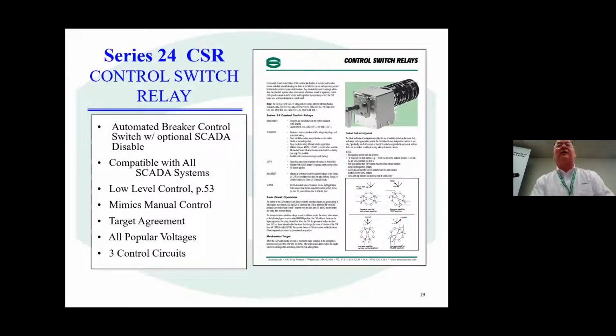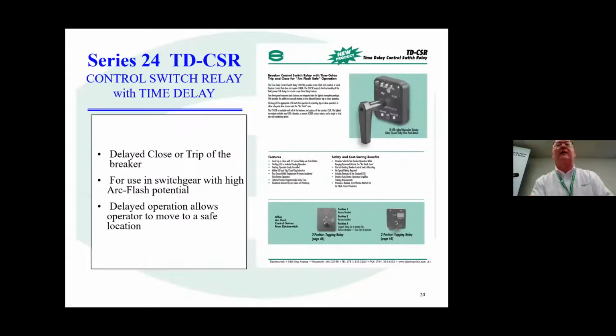So now we're going to talk a little bit about a special control switch. This is essentially taking a manual switch and putting a solenoid on it to electrically operate it, and then to provide SCADA outputs, as well as allowing it to be manually operated or SCADA operated, and then looking at the different types of configurations you'd want to have in this as a control switch relay. And this is primarily for time delay applications or automatic control applications.